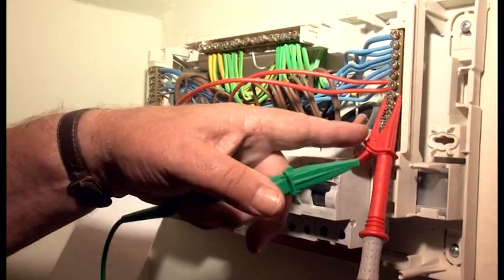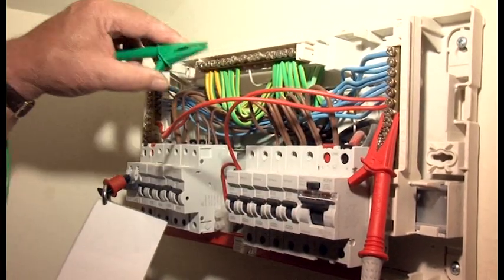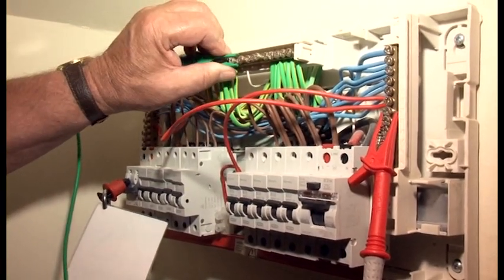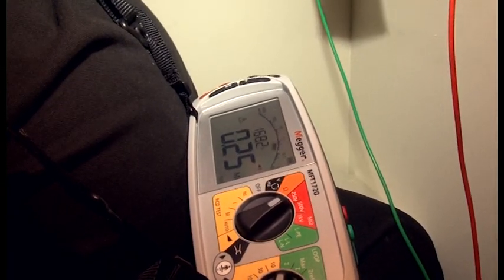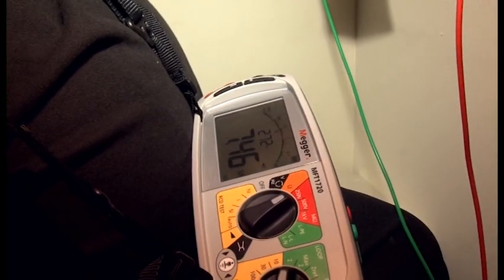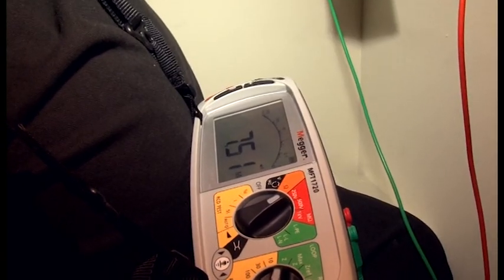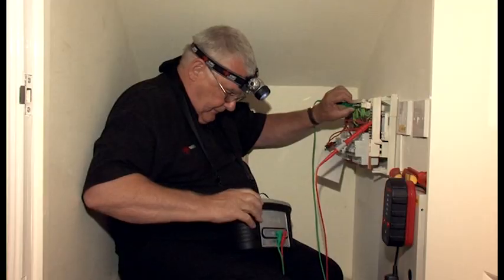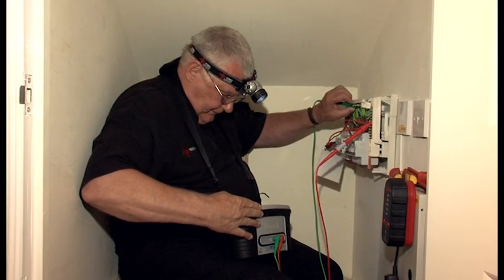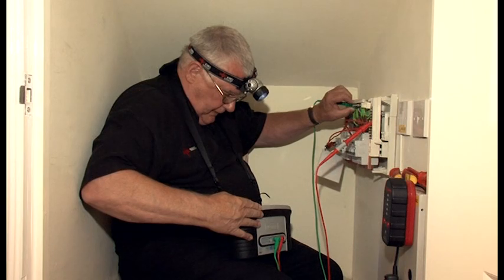Right then, as you can see, I'm on the line and neutral connected together. So let's go on to the earth. Let's do our test. And as you can see, we got a reading of 7.5 megohms. Well, I'm happy with that reading, so I will now test at 500 volts. Press the test button. And I have a reading of 7.53 megohms, which is more than acceptable.